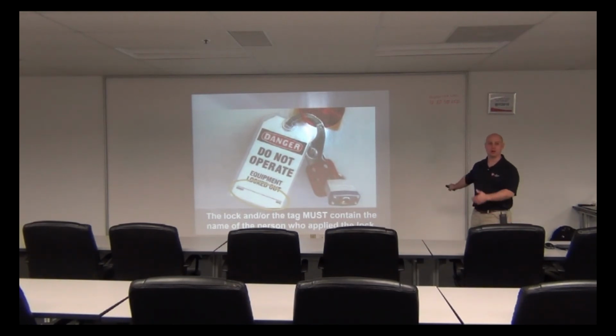I'm like, it's not even off. That didn't control it at all. So you have to find a disconnect on a wall at that point. I like that better. Not saying you can't use something like that, but they do break, so make sure it functions properly before you use it as your absolute lockout point. That's kind of part of that verify step too, you know what I'm saying? It goes back into it.